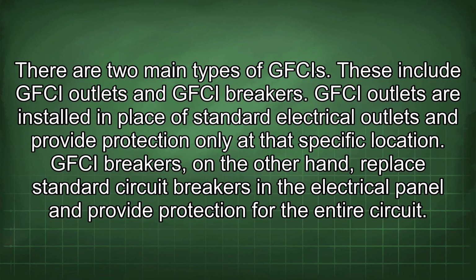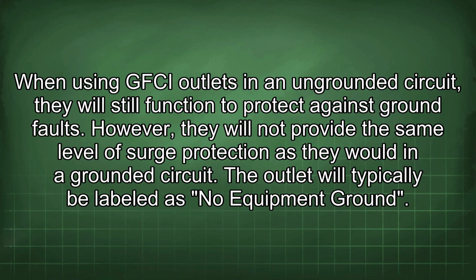There are two main types of GFCIs. These include GFCI outlets and GFCI breakers. GFCI outlets are installed in place of standard electrical outlets and provide protection only at that specific location. GFCI breakers, on the other hand, replace standard circuit breakers in the electrical panel and provide protection for the entire circuit. When using GFCI outlets in an ungrounded circuit, they will still function to protect against ground faults. However, they will not provide the same level of surge protection as they would in a grounded circuit. The outlet will typically be labeled as no equipment ground.